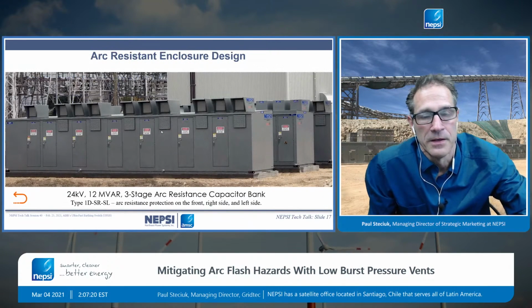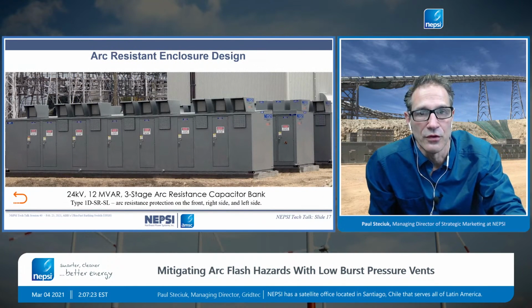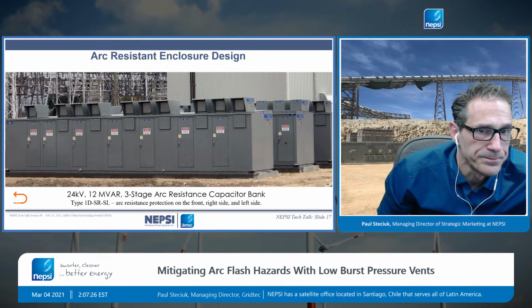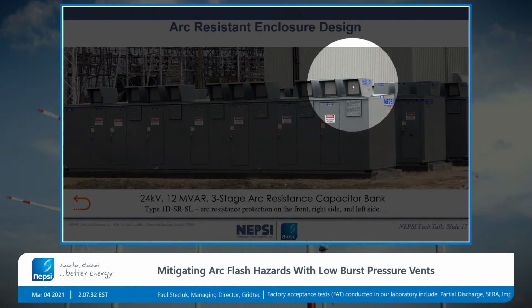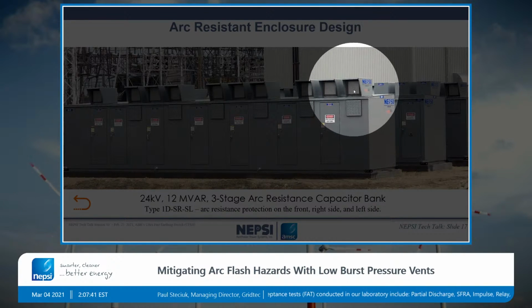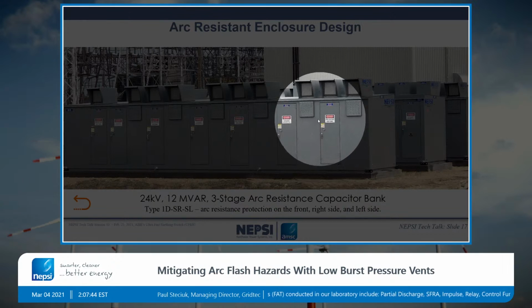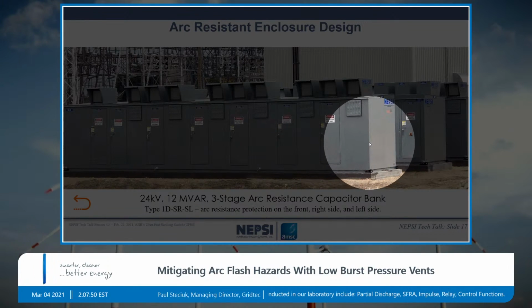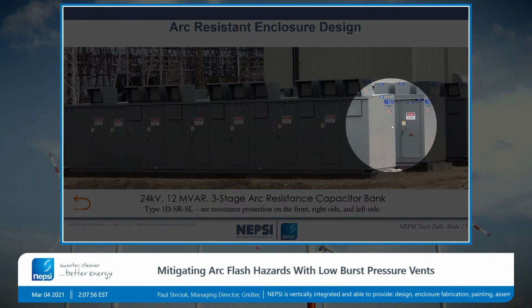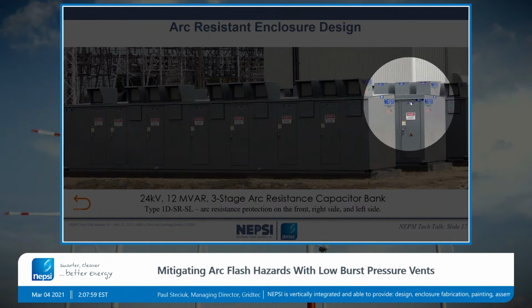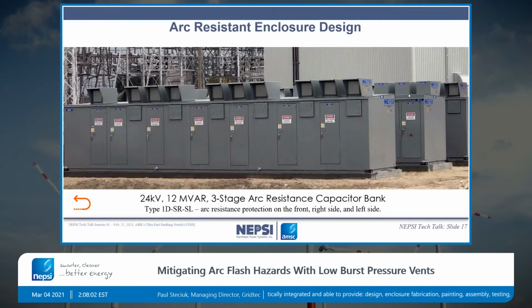It's quite interesting. Here's an example of an arc-resistant enclosure that NEPSI has built. Here you can see that we have put on top the release area where the arc will exhaust out. You can note here that we have intake vents, and these things also act as exhaust vents. And the premise behind this is if there's some type of arcing fault within here, you're going to get a very fast pressure buildup. The inside of the enclosure is going to get very hot, and that gas must go somewhere, and the objective here is to expel it out. The space in between these enclosures, you can see these are facing the opposite direction, would be considered a safe zone.